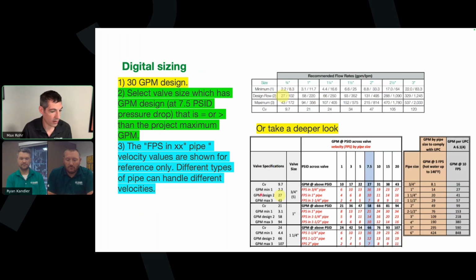So we'll take a look at the more complex chart here. We've got 27 GPM design, but what does that mean for the pressure drop? So we're somewhere between 7.5 and 10 PSI drop across that valve in this 30 number that we had, closer to 10. So if we were to use 3/4 inch pipe throughout the building, we'd be moving like 16 to 19 feet per second. That is screaming fast. You would hear that. That's moving way too fast. That's not good. We would not recommend piping the building like that.